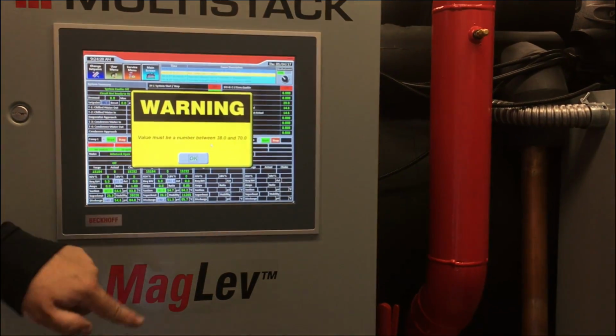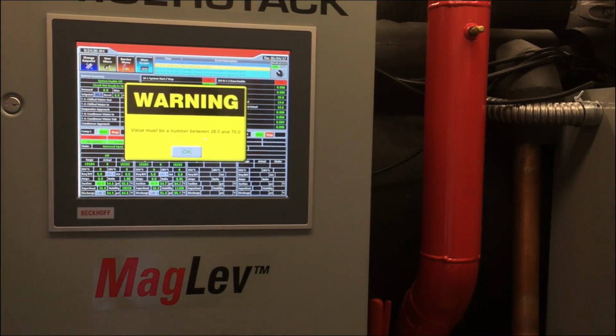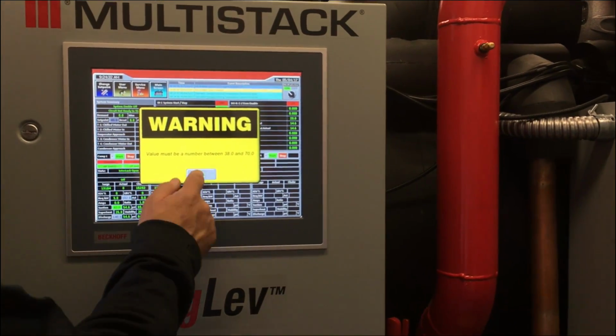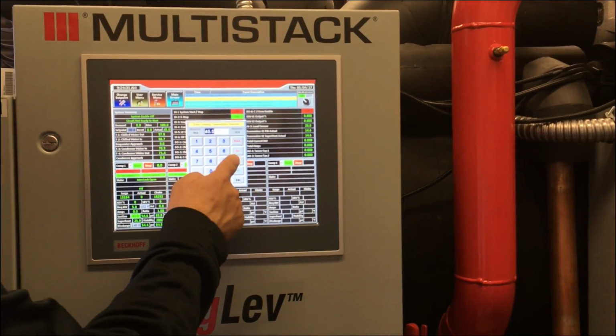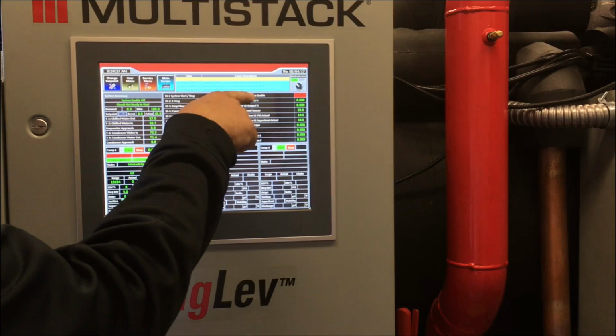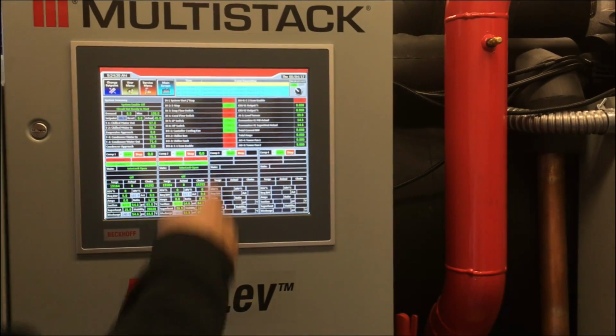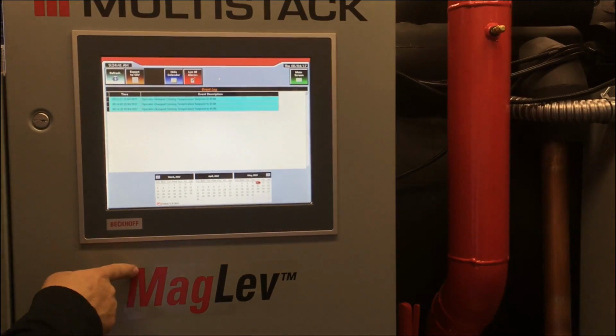If I go 9, enter, see, valid number must be between 38 and 70. So that's our range. So we'll hit OK. I'm going to hit escape. So we still see operator change cooling temperature set point to 45. So now I have something to look at today.